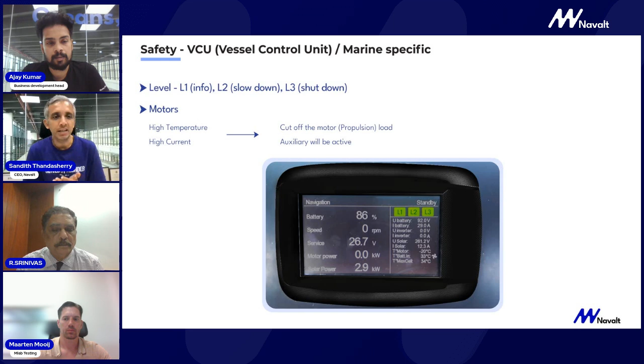In a solar plant, since most of our boats have large solar arrays, typically the MPPT side protection is decided based on the pack voltage level, which determines the cut-in and cut-out points. But if there's communication between the BMS and the MPPT, requiring a vessel control unit layer, then even if an individual cell has a slightly higher voltage than the prescribed limit, you can force a shutdown of the solar plant itself. That's something additional we tend to do.